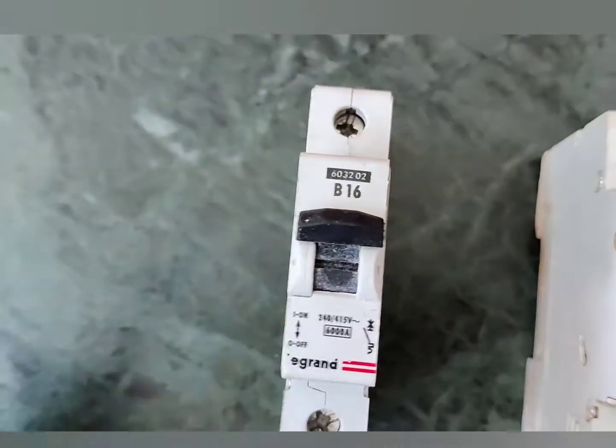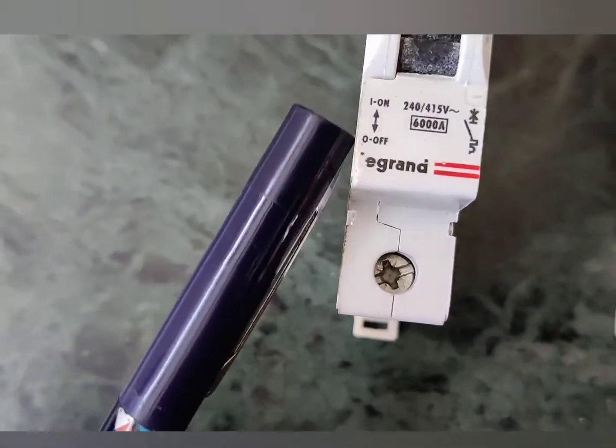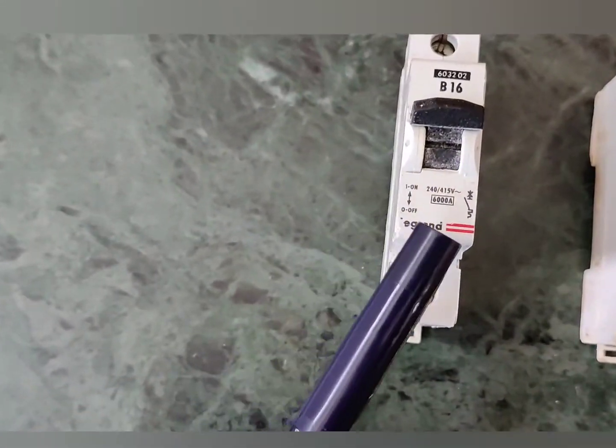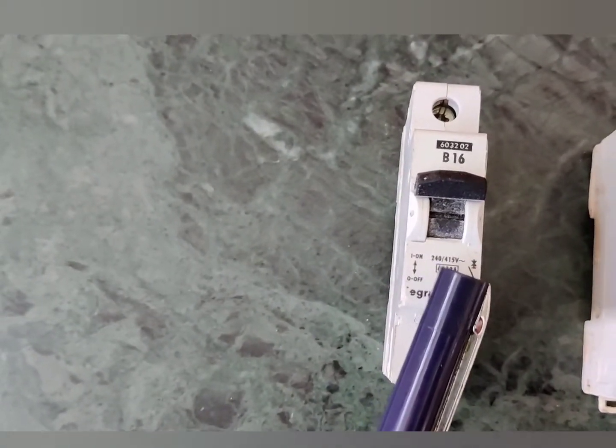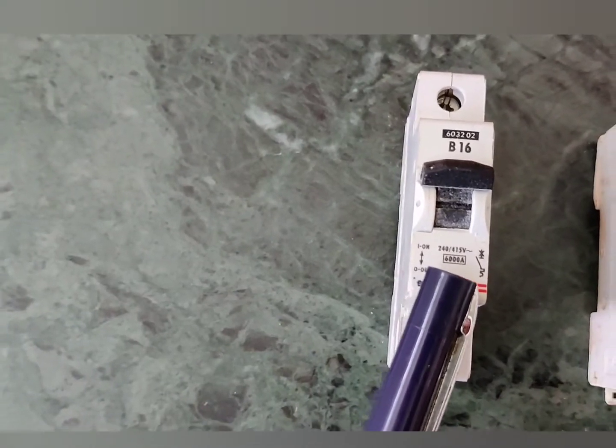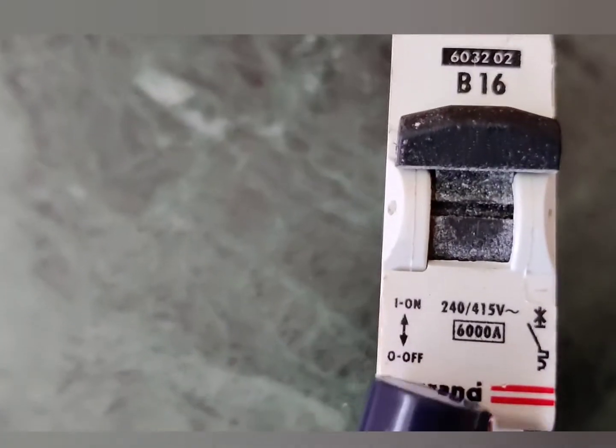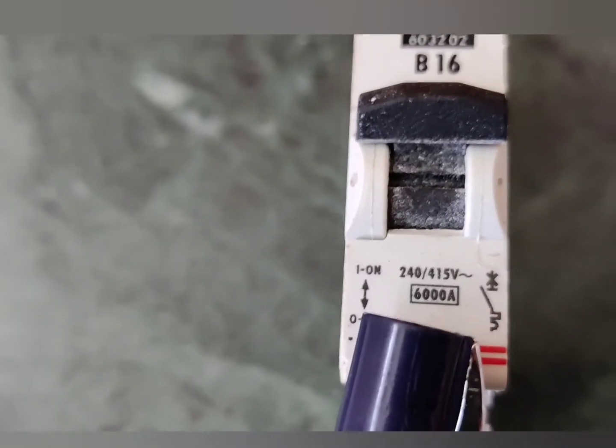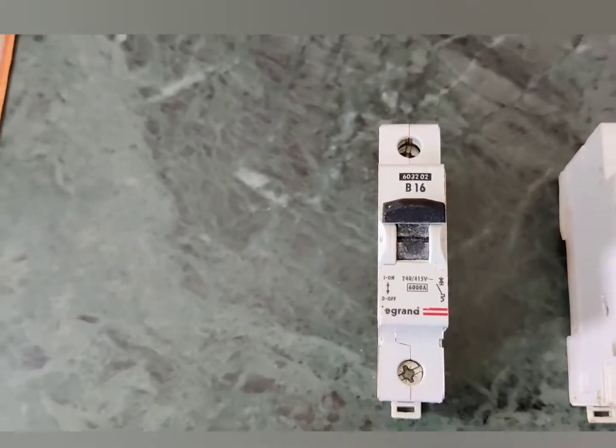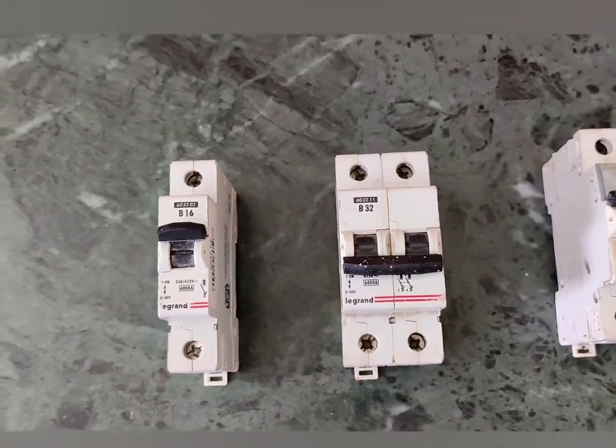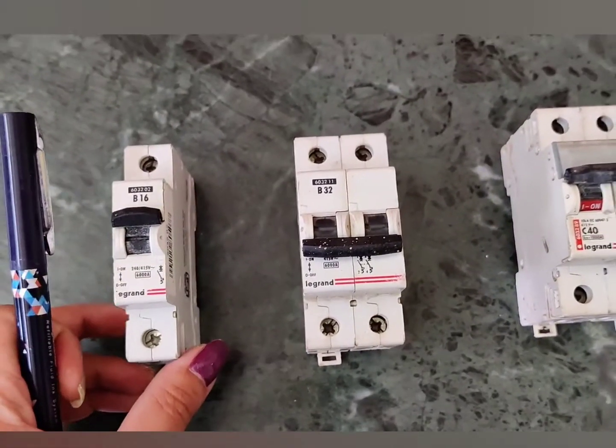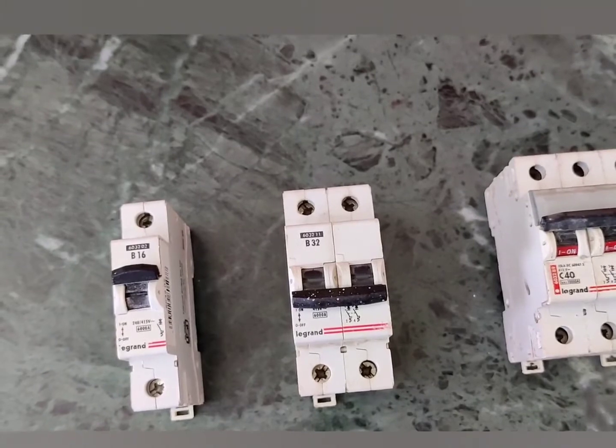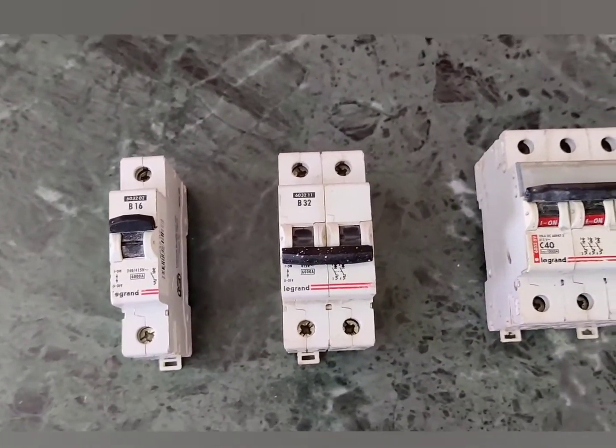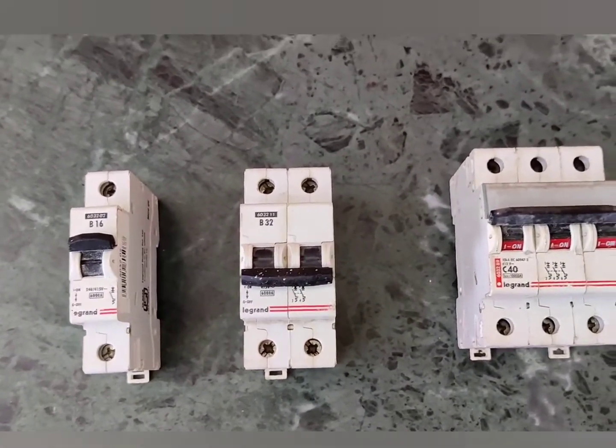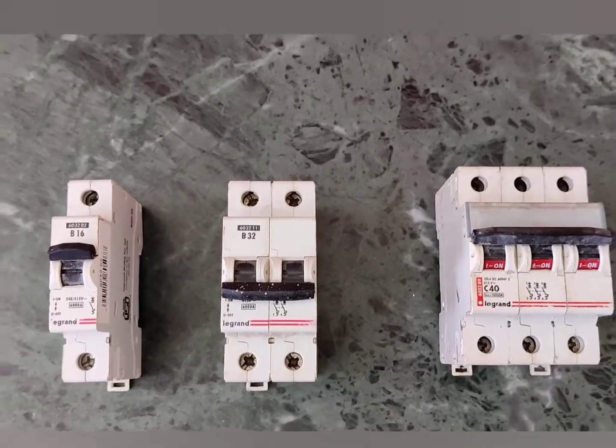Then here we can see that the on/off position is indicated on this MCB. This is the operating, or you can say rated voltage, 240 or 415 volt depending on our application, and this current rating that is shown over here, 6000 ampere. This is the breaking capacity of this MCB. That means breaking capacity stands for how much current this particular MCB can withstand without getting damaged. So that is the breaking capacity.